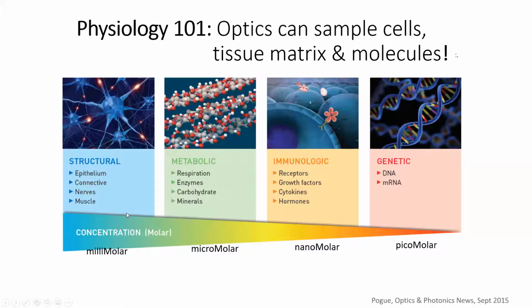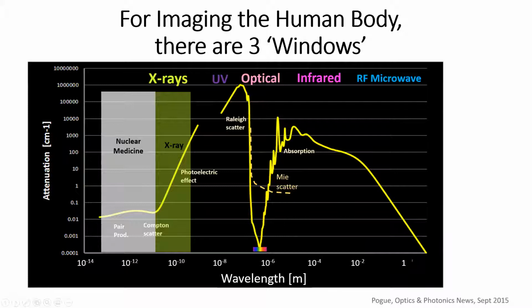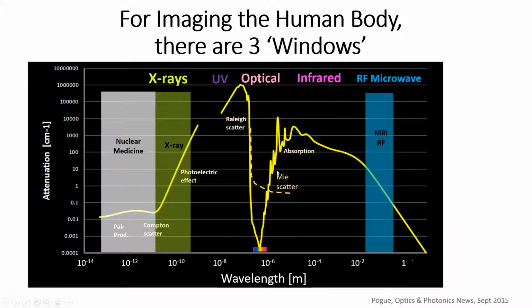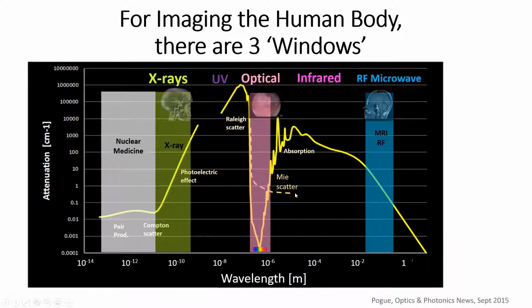There's low attenuation in the X-ray gamma range. We use that for nuclear medicine and X-rays. There is low attenuation in the radio frequency range, and we use that for MRI. And then there's reasonably low attenuation in the optical near infrared range, and we use that for optical imaging. You can see examples of X-ray imaging, MRI imaging, and then optics. And optics does have this elastic scatter component, which limits it. But still, we can get light through millimeters to centimeters of tissue, depending on how the device is designed.